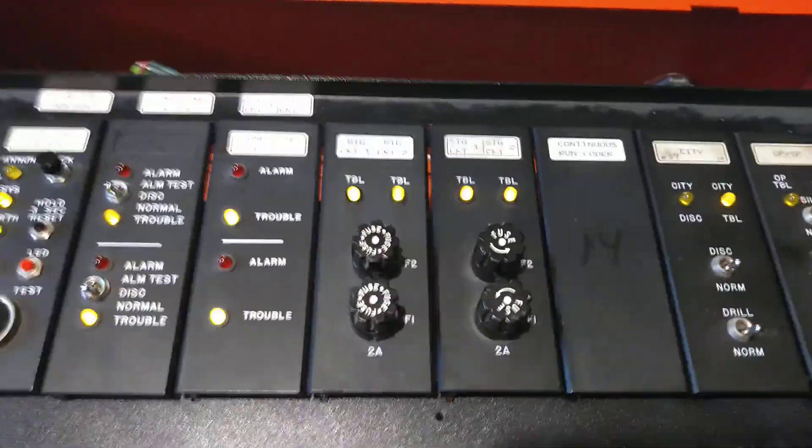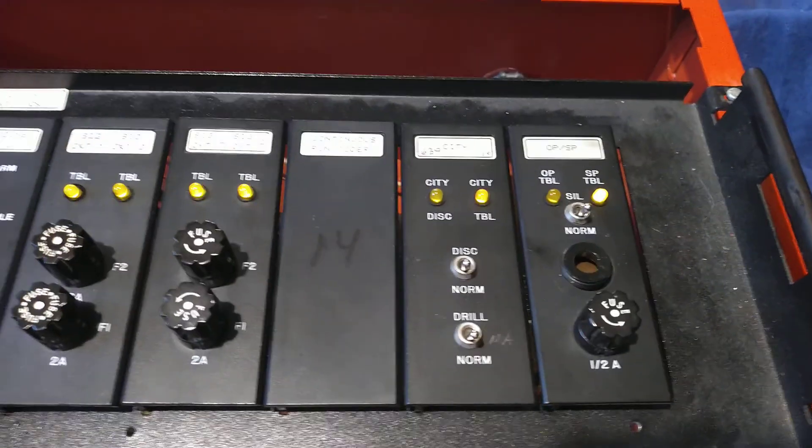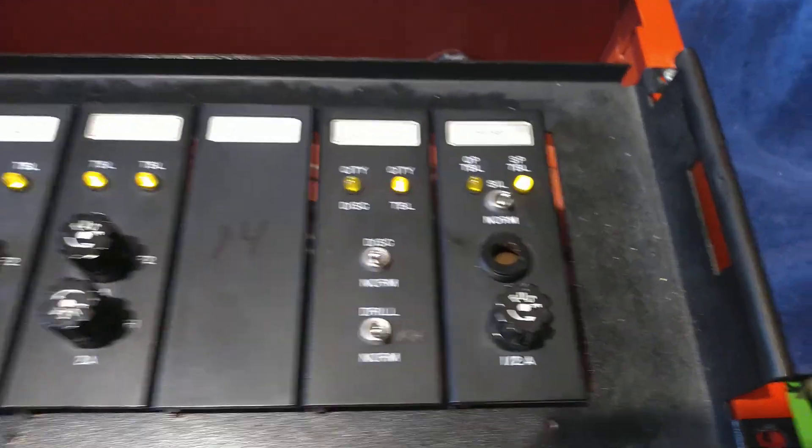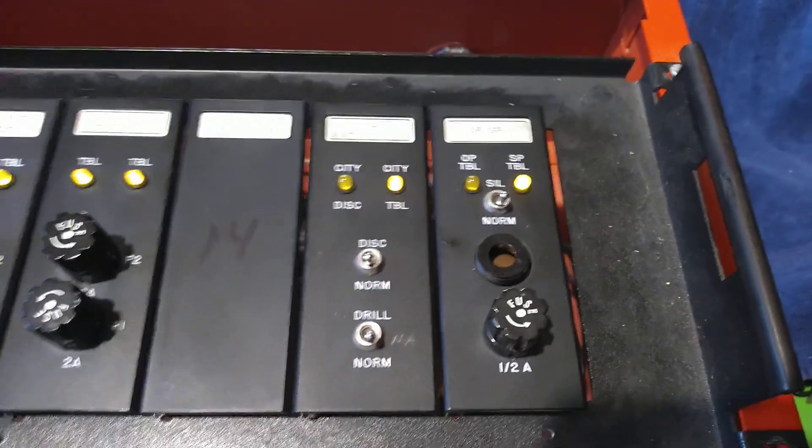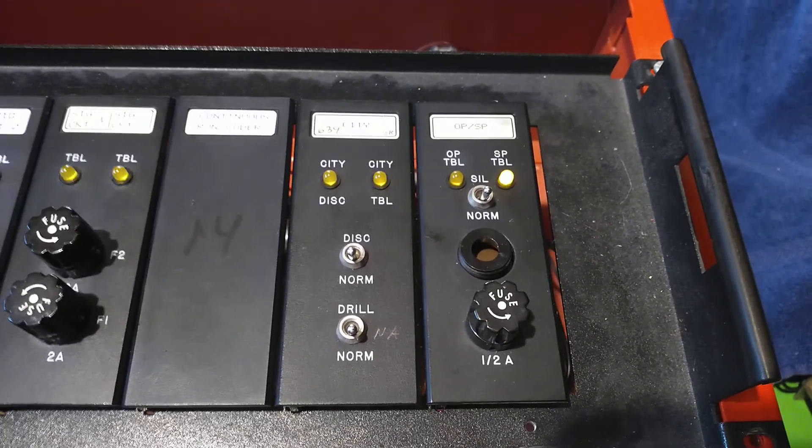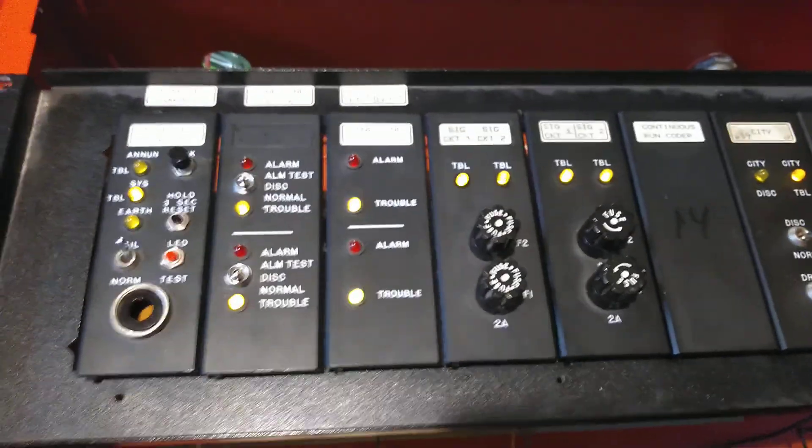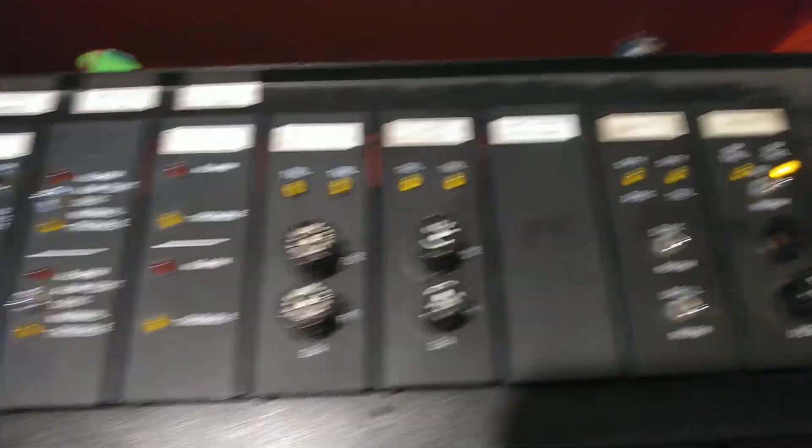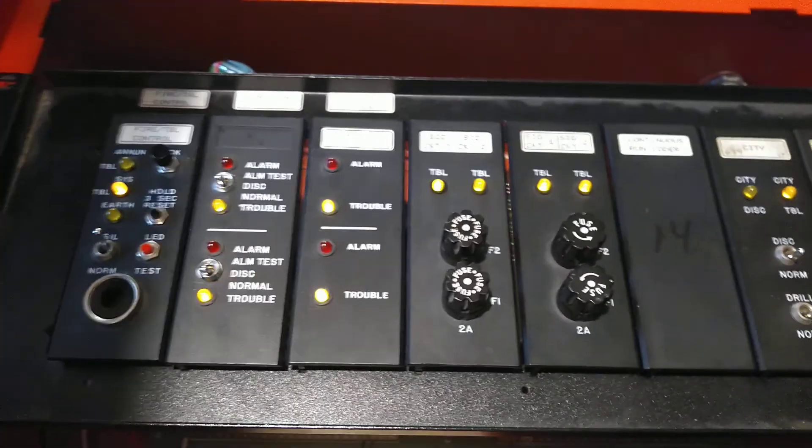I still have a whole bunch of troubles. No end of line resistors are put in. I do not have a city box yet, and I still need to get a secondary power supply for the OPSP card. But I think I have everything pretty much figured out. I just need to get the parts and put everything all back together and make the panel completely happy.